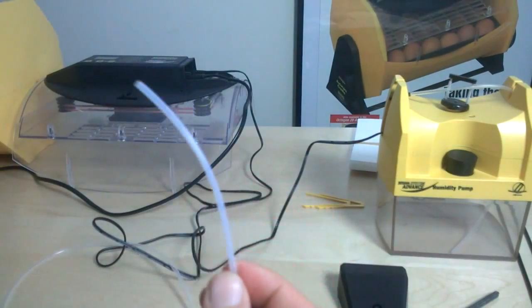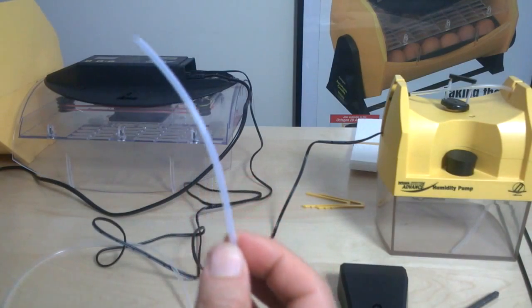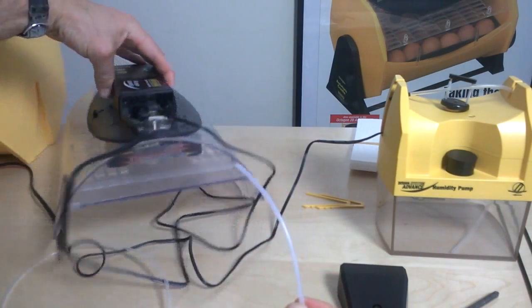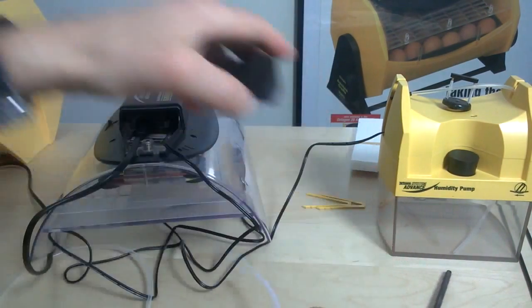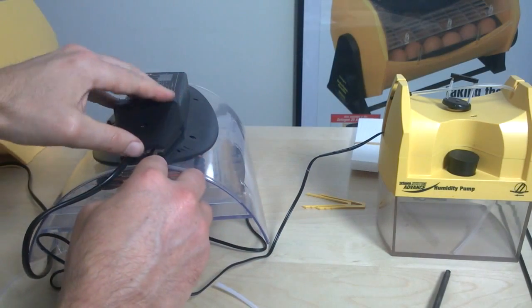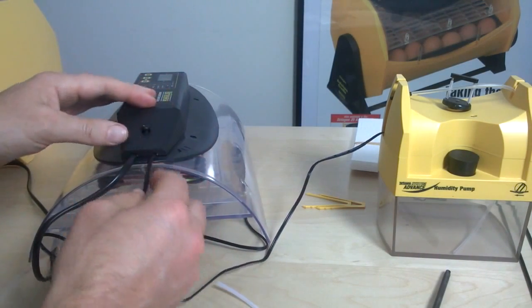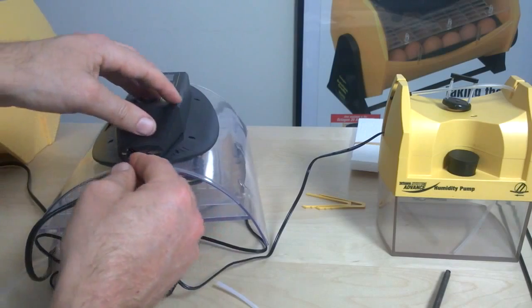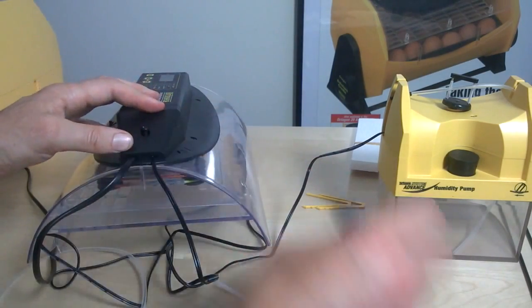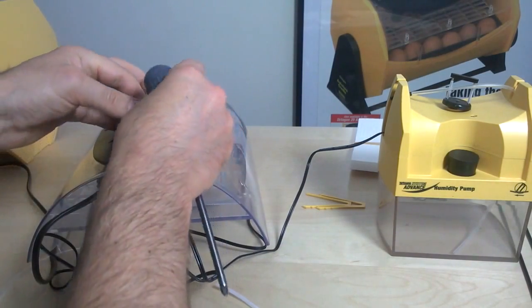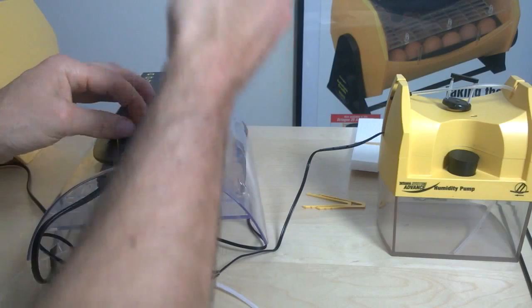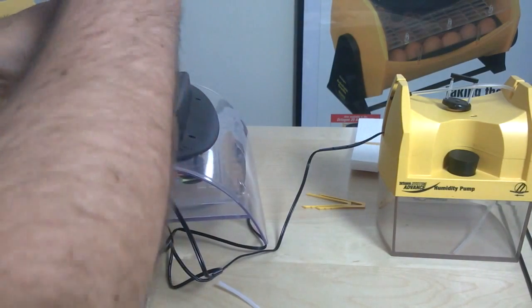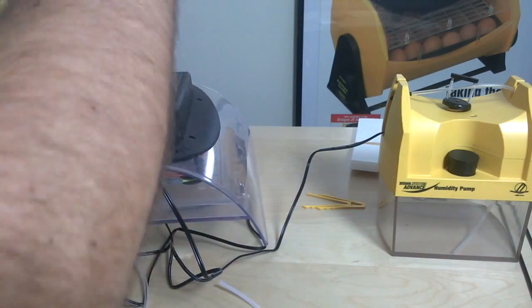Okay, so when we've overlapped that by about a centimetre, as I've done here, we can position this into the lid of the incubator. Now, before we do that, we ought to make sure we place our cap back over the electrics without trapping any of the wires, and fix that lid back down again with a little screw that we've got, which can drop out if it's slightly magnetized, or if the screwdriver is magnetized. There we are. So just fix that back in, making sure we don't trap any of these wires, just to protect the electrics.